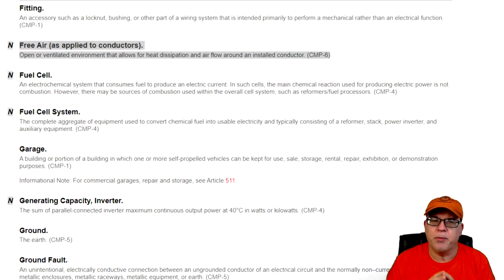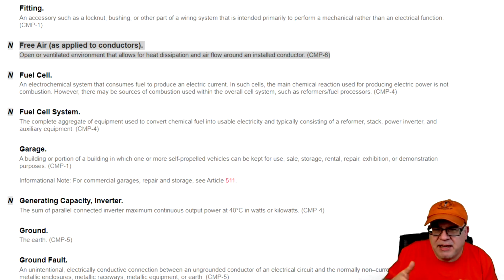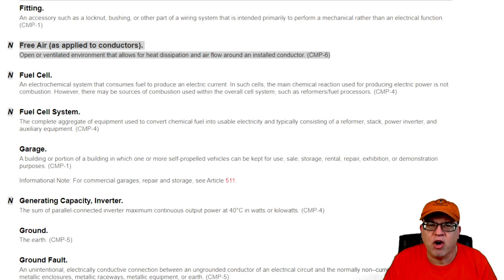Now, free air is important because when you run cables together, like in cable trays, you're not really separating them, but everybody wanted to use the allowances of free air and ampacity values in 310.15(B)(17), which was in the 2017 code. Now it's just 310.17. They wanted to use those free air values for ampacities, which are higher than the normal 310.16 that we're dealing with. But if those conductors weren't separated, had a separation, and what was the minimum separation? What constituted that application? It got a lot of arguments.